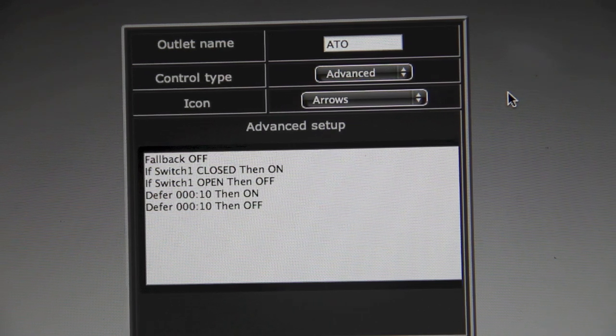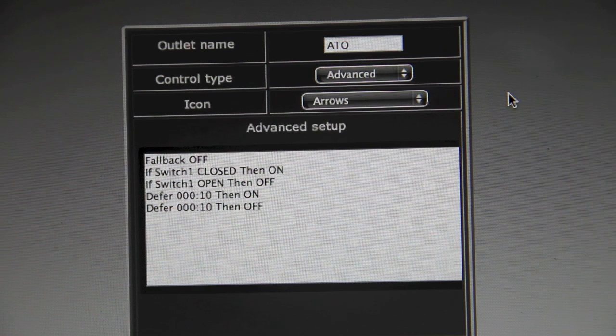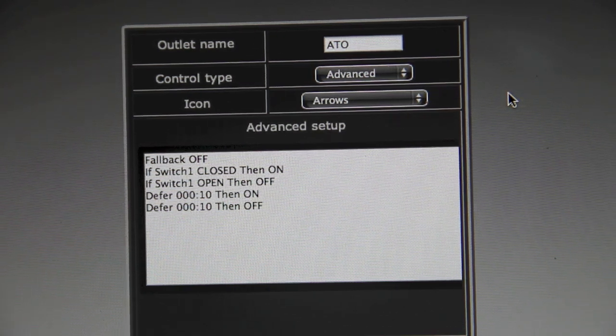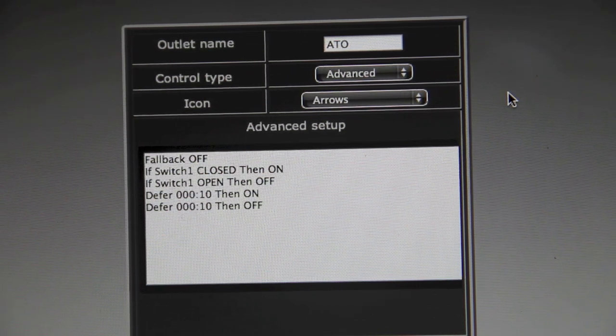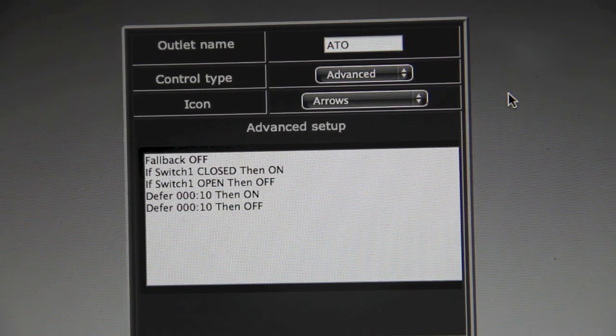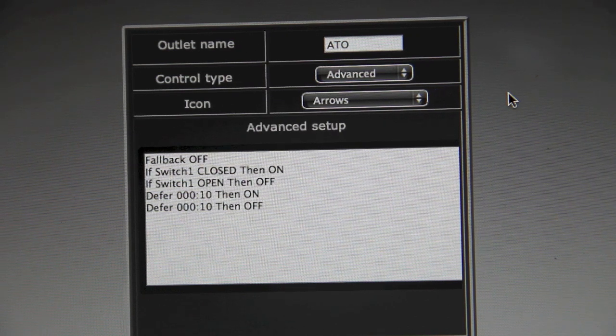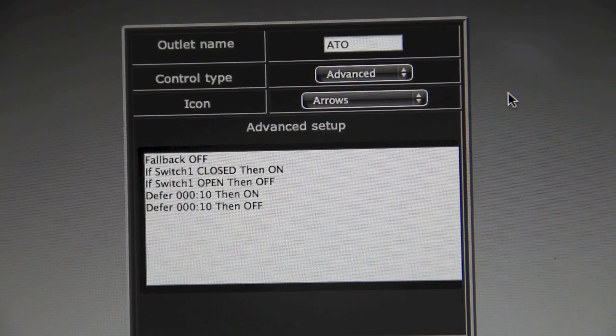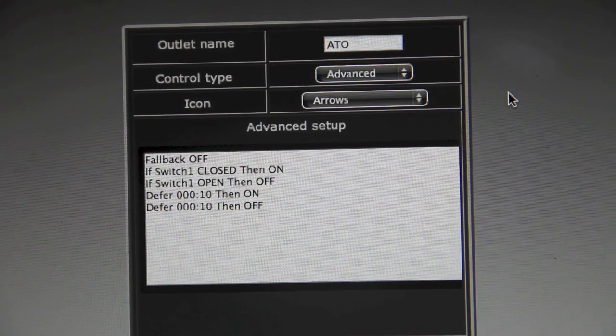If it's floating, it shuts off. When it closes, it'll kick on until it starts to float, then it'll shut off. The 10-second defer on and off is because if you stick your hand in the sump and splash around, the water creates a little wave that makes the float switch go up and down, and you don't want the auto top off to kick on and off for that. So there's a 10-second delay: it takes 10 seconds for it to kick the auto top off on, and it won't kick on or off unless it's up or down for a full 10 seconds. Just another safety feature.